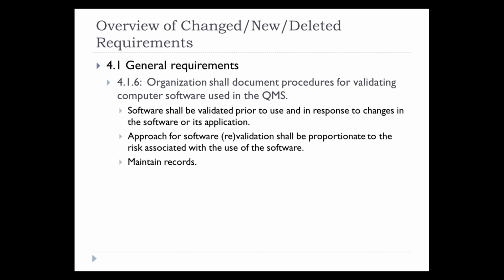So some examples to demonstrate differences in approach to the validation and revalidation process. If your computer software is an integral part of your medical device, the validation protocol, both initial and revalidation, would be very stringent. If you're using computer software, for example, for tracking calibration of the gauges used in your manufacturing processes, or using validation software, if you're using software for your maintenance program, the initial and revalidation protocol may not be as stringent.